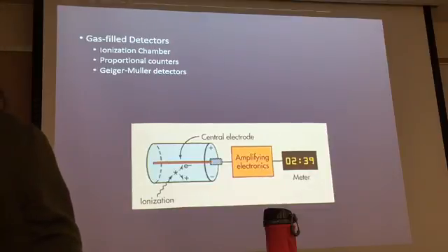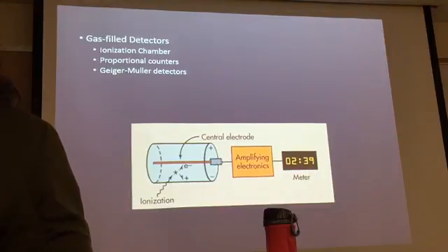This is the type of device that is used to calibrate X-ray equipment. It has to be calibrated not only to the energy of the X-ray equipment, but also to the timing. Remember, some of the exposures we do are 1 millisecond. So very short exposures, and these devices are very sensitive to that.